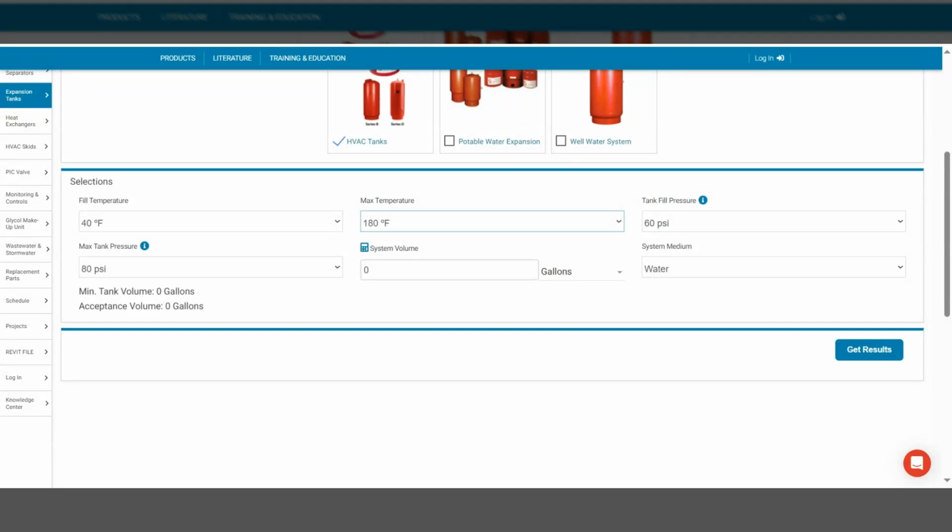That's because half of the temperature is the supply, half of the temperature is the return, and the average is the 160. However, when you have two-way valves in the system, if we don't have temperature reset, or if somebody changes it and leaves it at a set temperature of 180, on a beautiful spring day, if you send 180 degree water out, you are not going to get 140 degree water back.